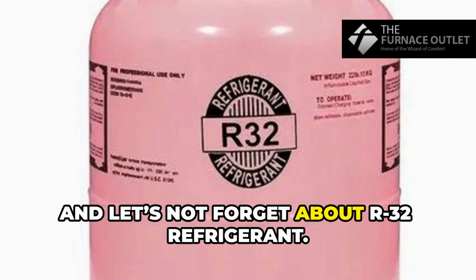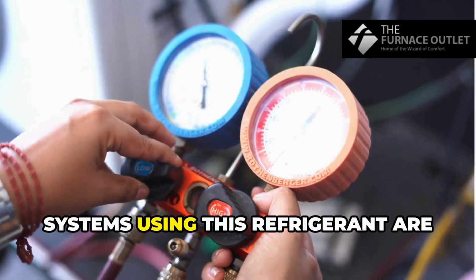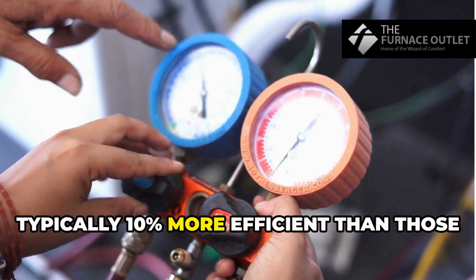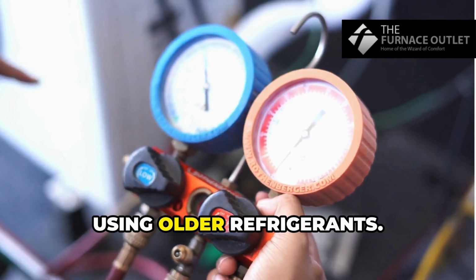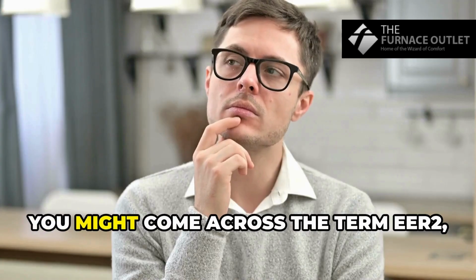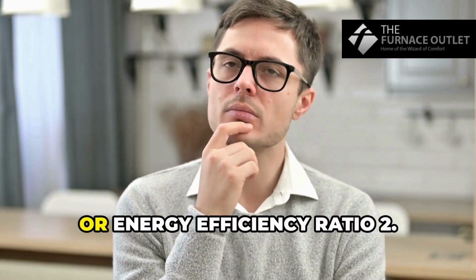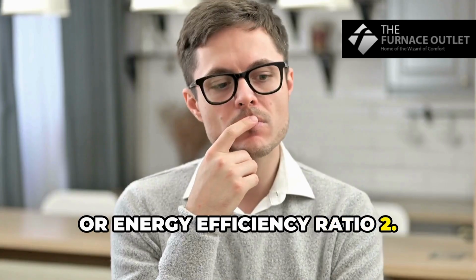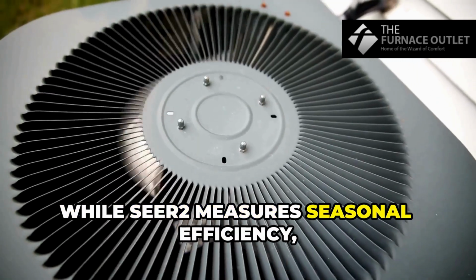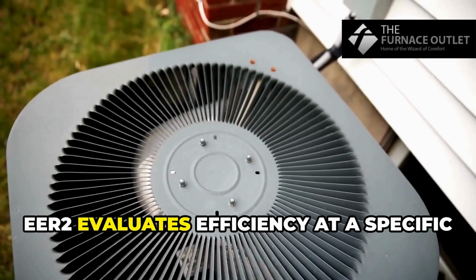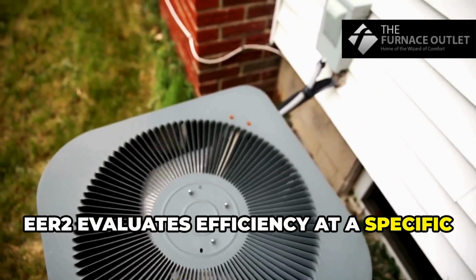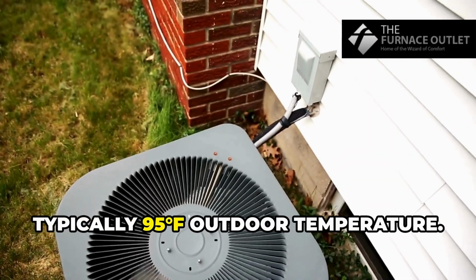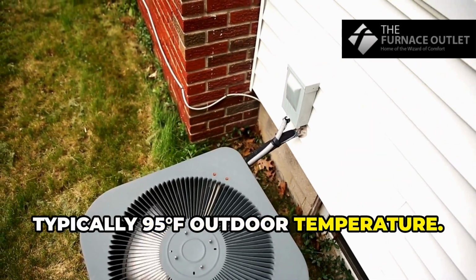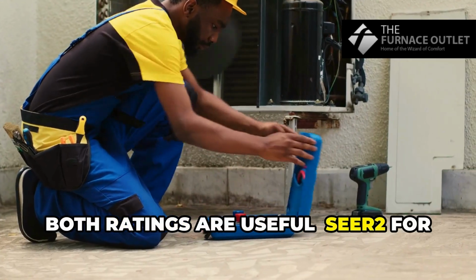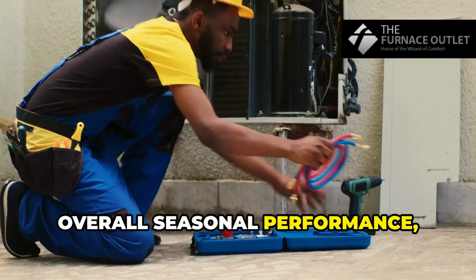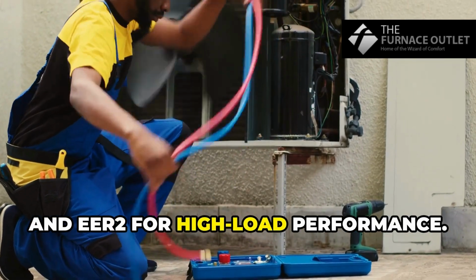And let's not forget about R32 refrigerant. Systems using this refrigerant are typically 10% more efficient than those using older refrigerants. Lastly, you might come across the term EER2 or Energy Efficiency Ratio 2. While SEER2 measures seasonal efficiency, EER2 evaluates efficiency at a specific operating condition, typically 95 degrees Fahrenheit outdoor temperature. Both ratings are useful. SEER2 for overall seasonal performance and EER2 for high load performance.